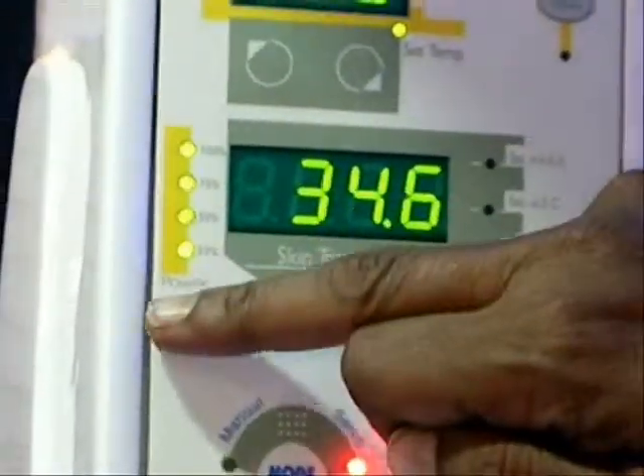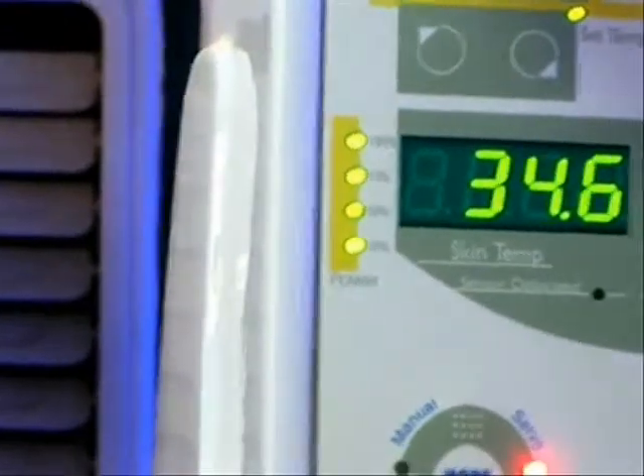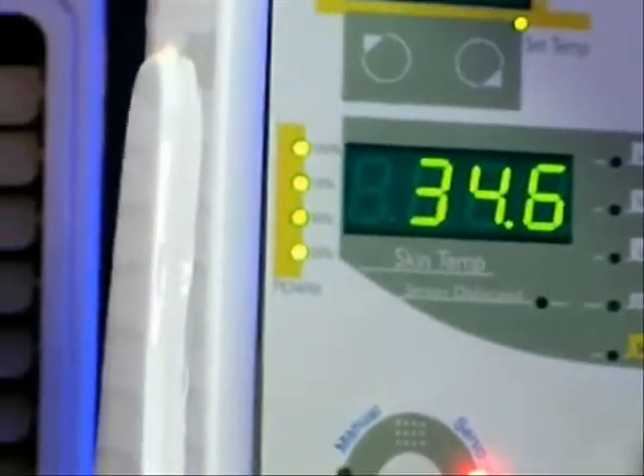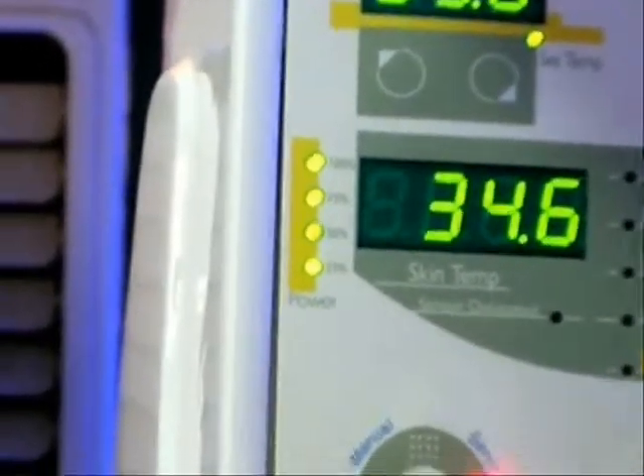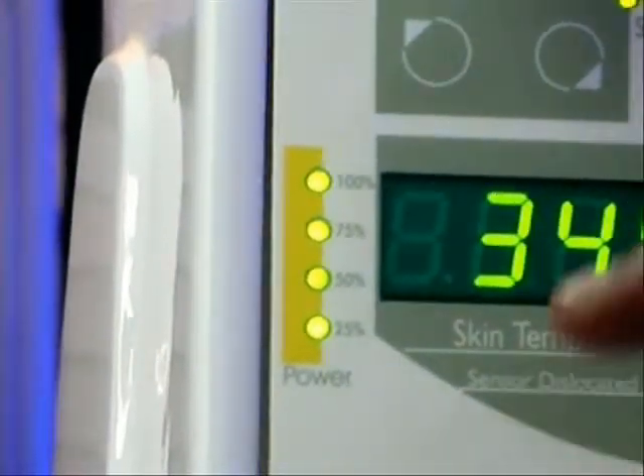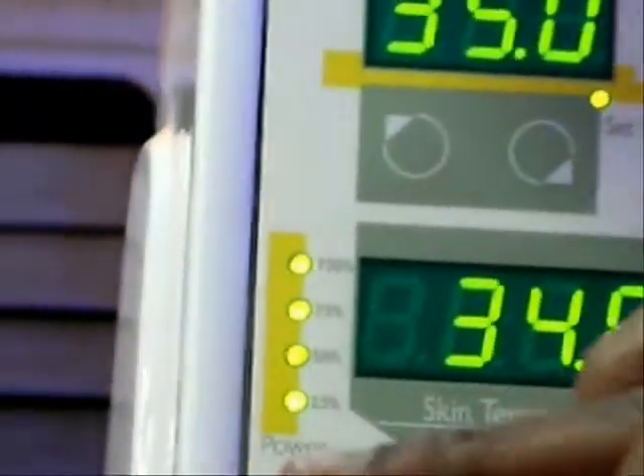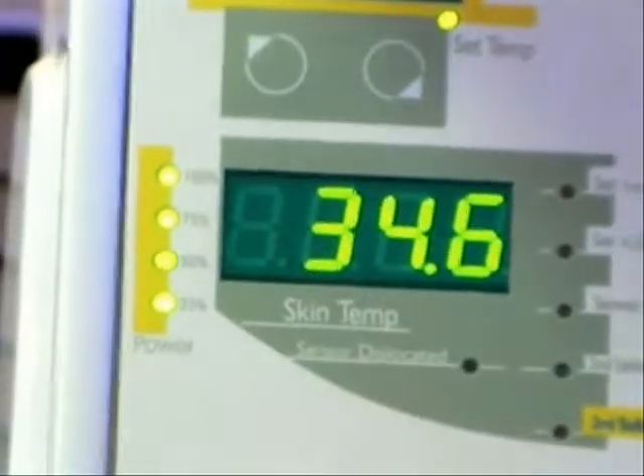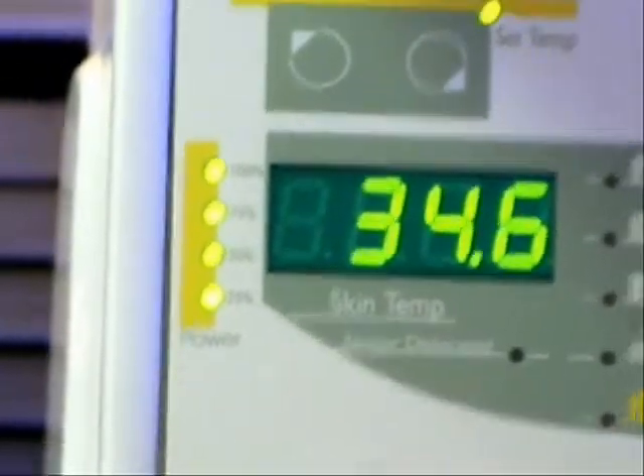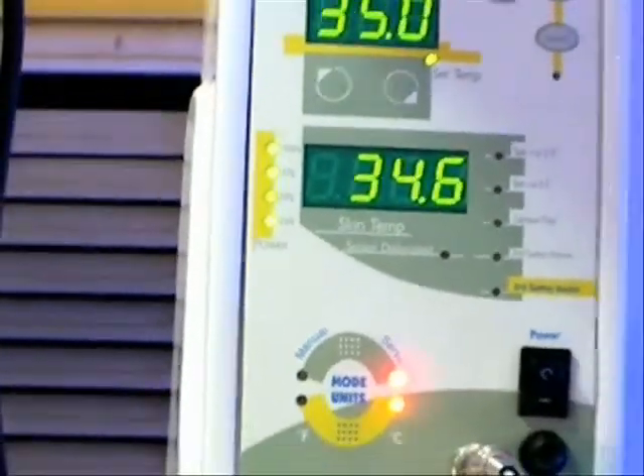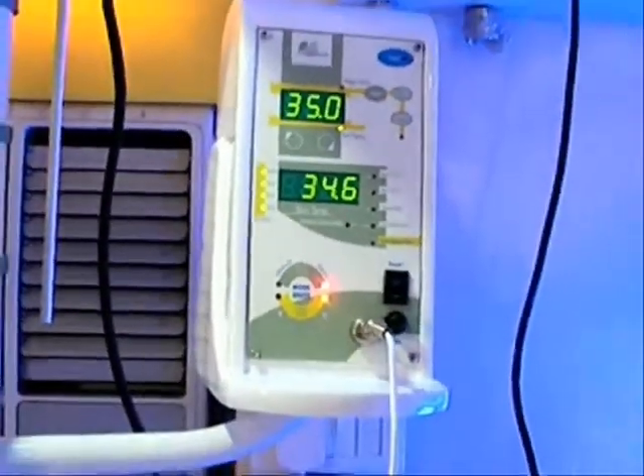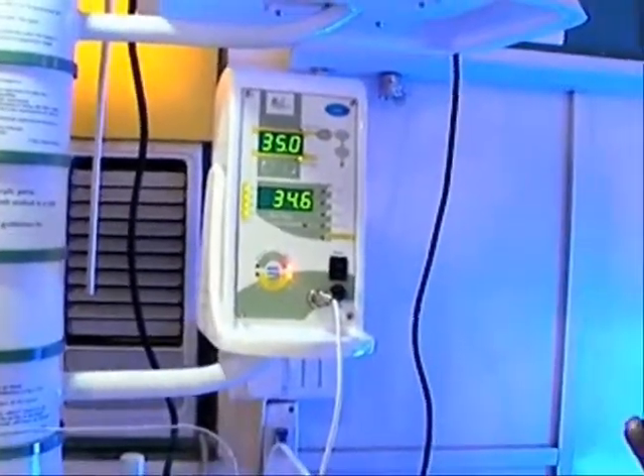Plus, you have a proportional system. Initially, the heater consumes 100% of the power. But as the baby's temperature starts reaching the desired level, the power to the heater is reduced proportionally. So it achieves two things. One, it saves your electricity. Two, it ensures that the baby's body temperature is maintained very precisely and is absolutely safe for the infant.